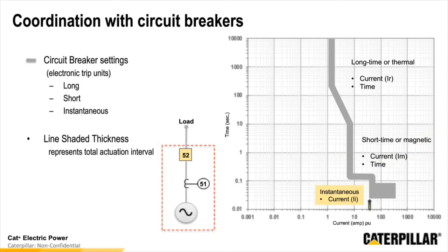And the last portion is the instantaneous trip. The instantaneous trip is really where we're going to try and set the unit so that we know we're going to trip off as soon as we receive or identify that the current has reached that point. That's going to be an instantaneous trip. There's typically only a current threshold for this because, as it states, it's going to react as soon as it can identify the current and open.